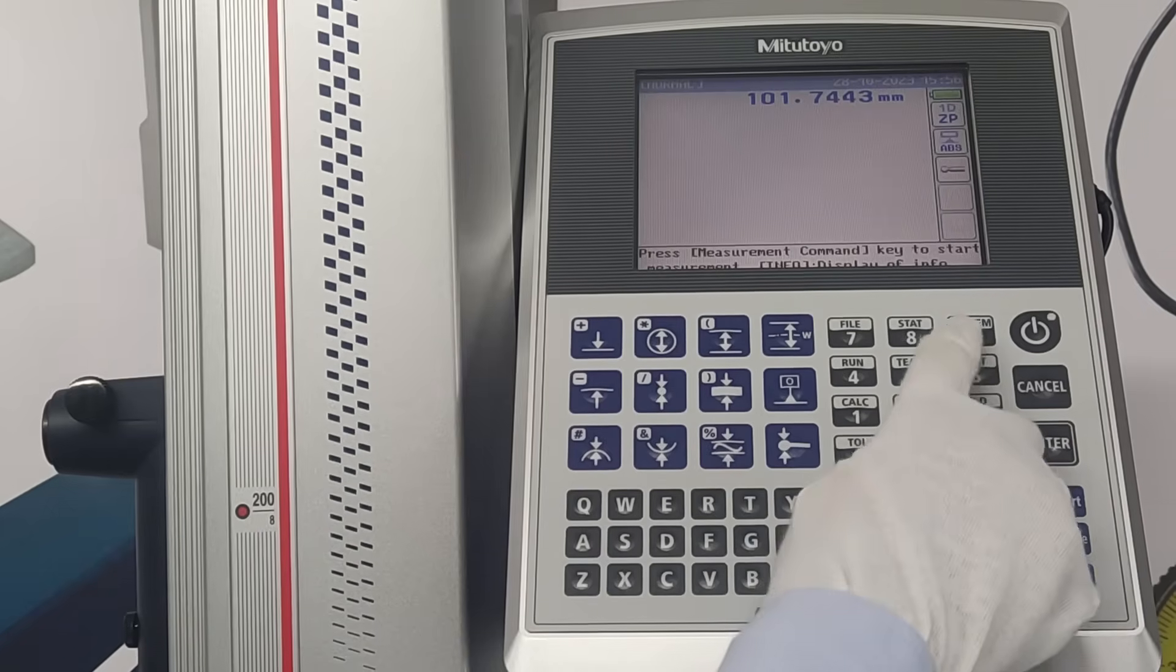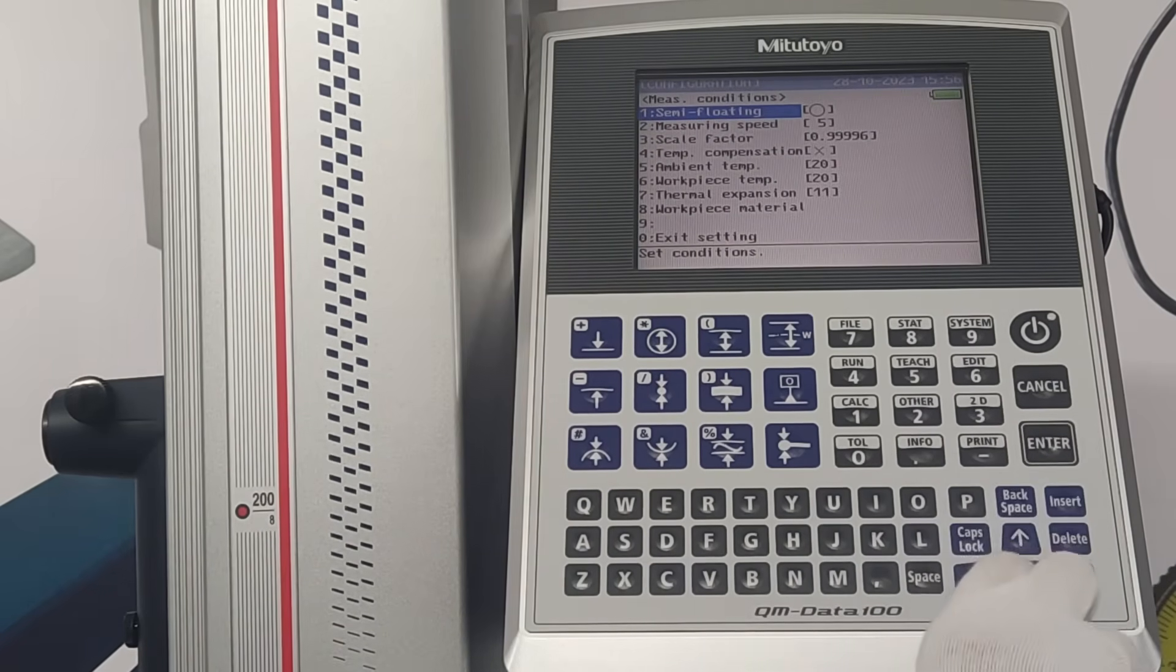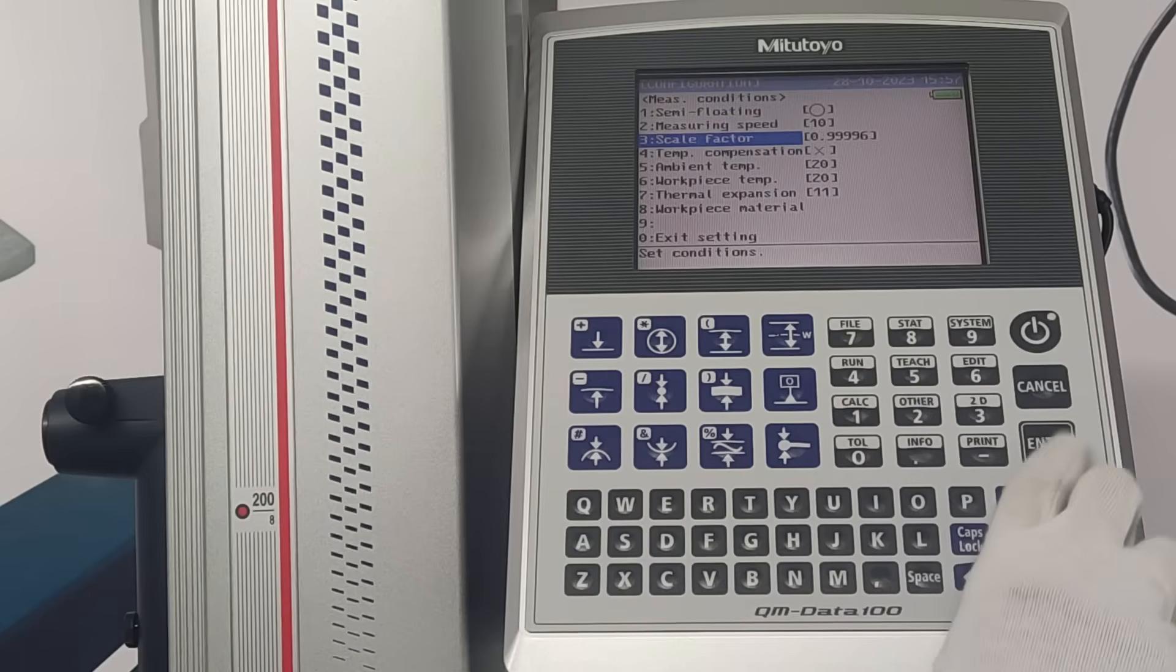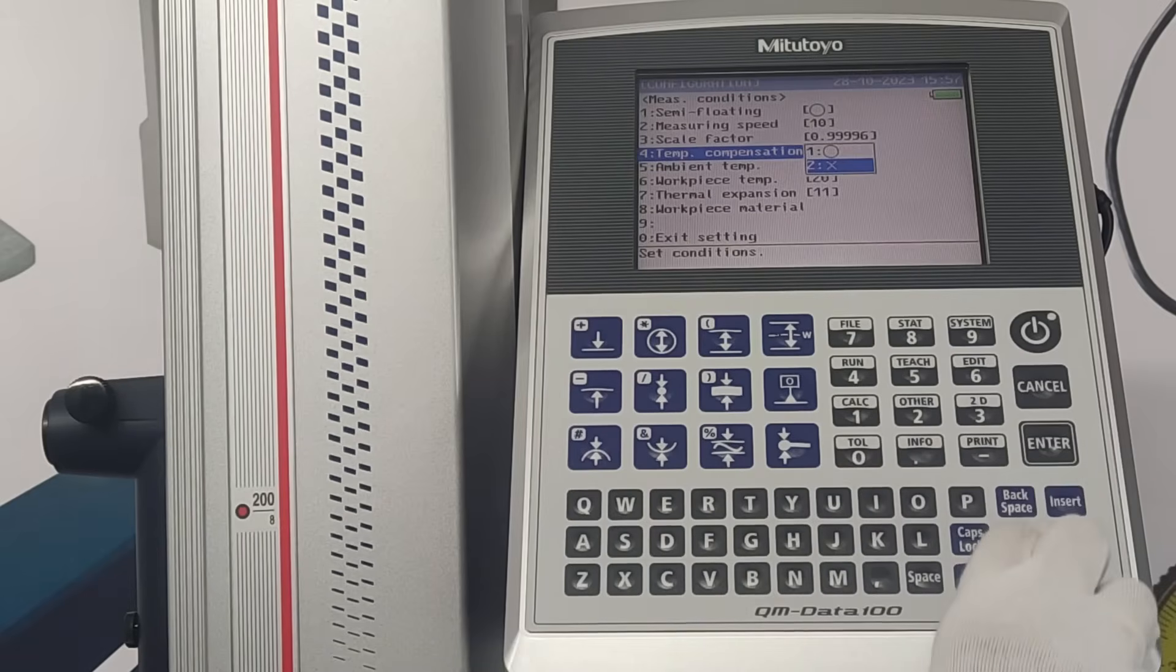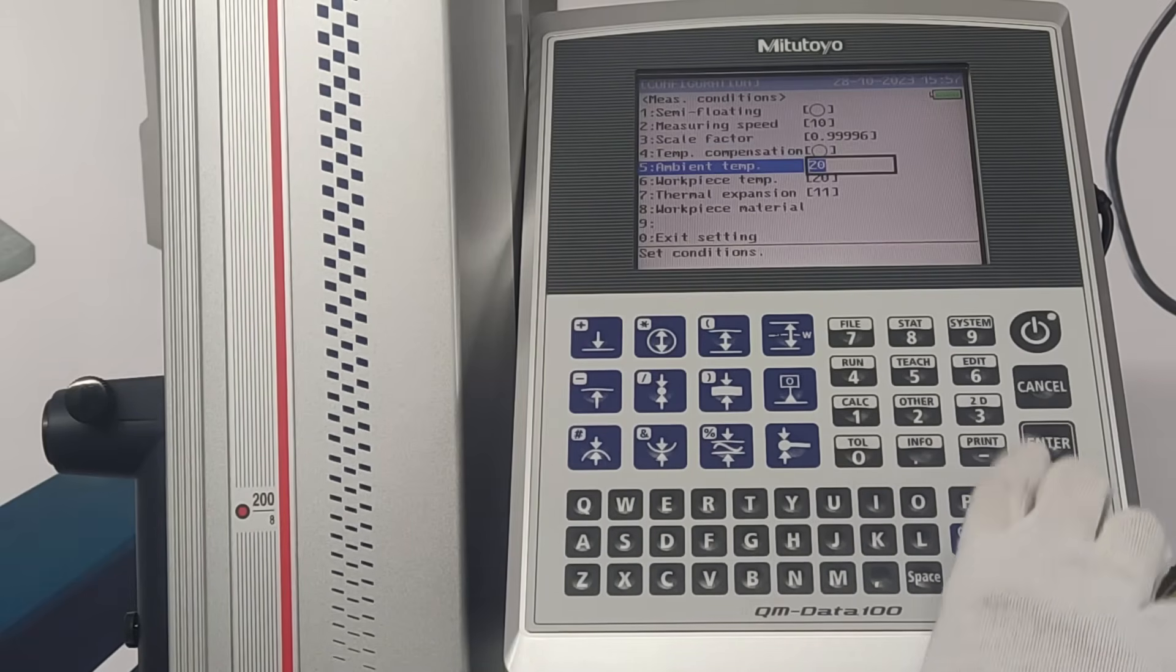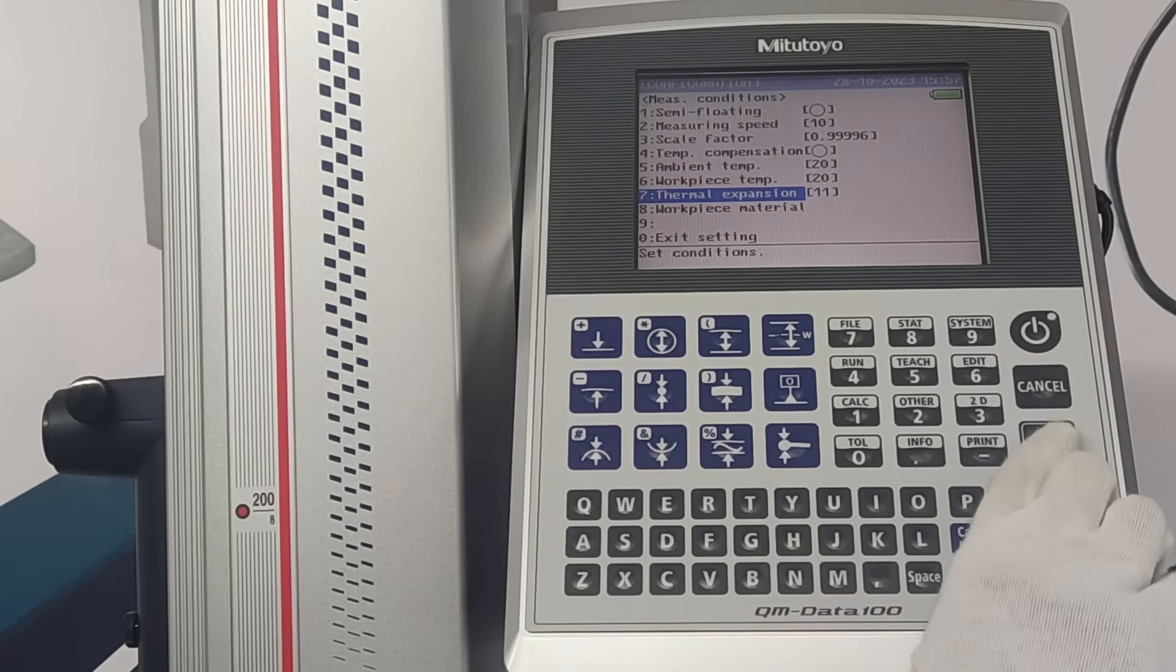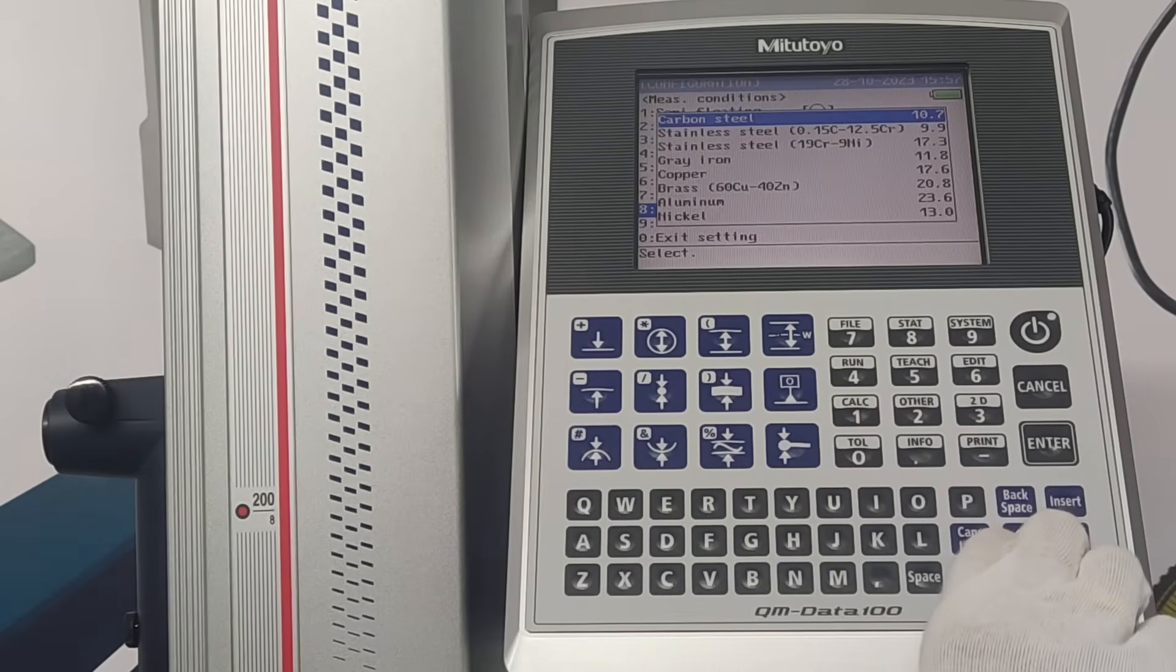In system configuration, under measure conditions, semi-floating can be turned on or off. Measuring speed can be selected. Scale factor can be adjusted. Temperature compensation can be turned on or off. Ambient temperature is set. Workpiece temperature can be adjusted. Thermal expansion can be defined. Workpiece material can be selected.